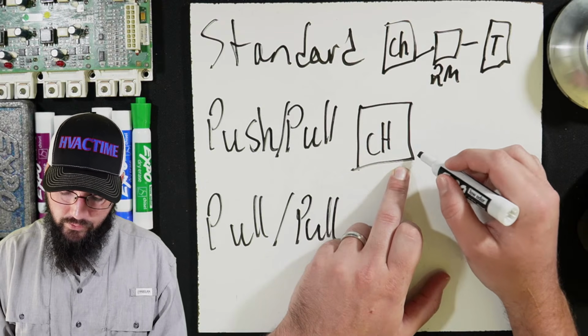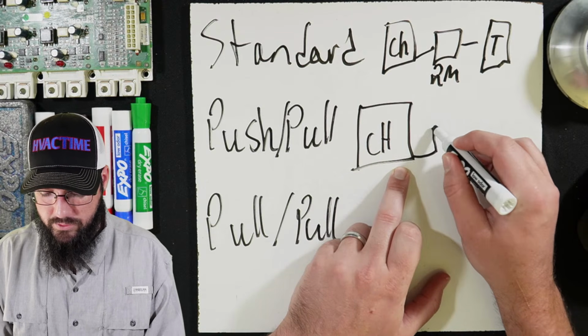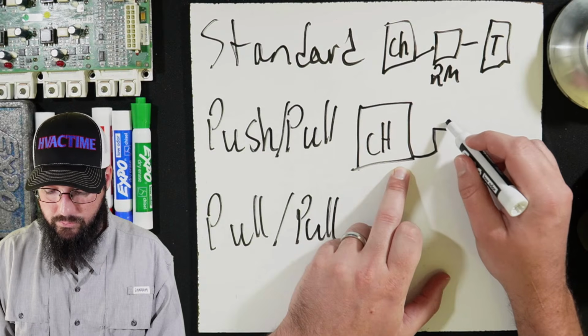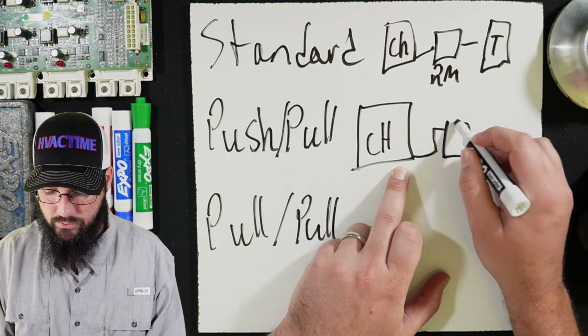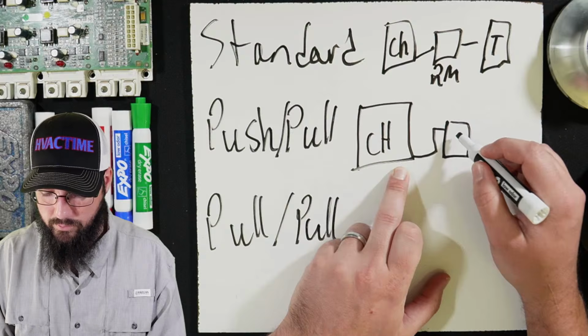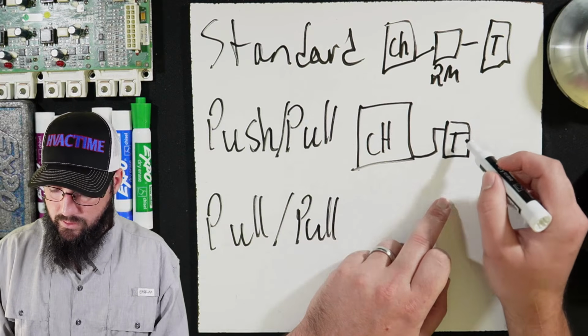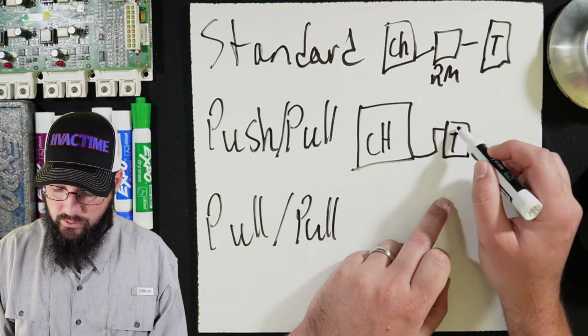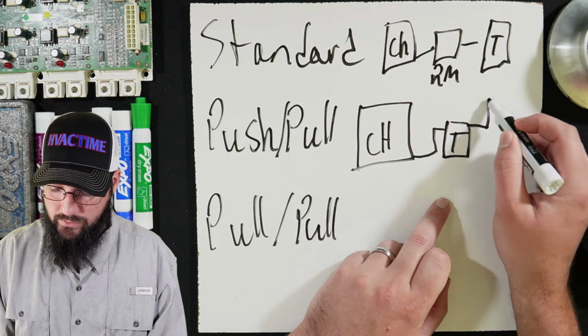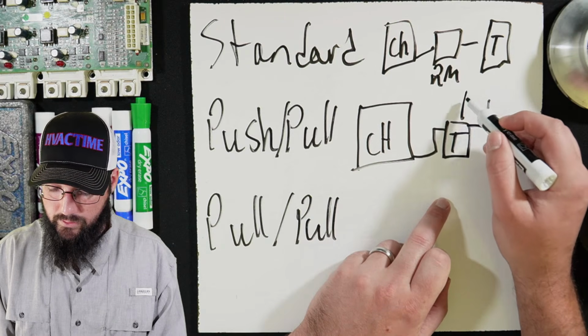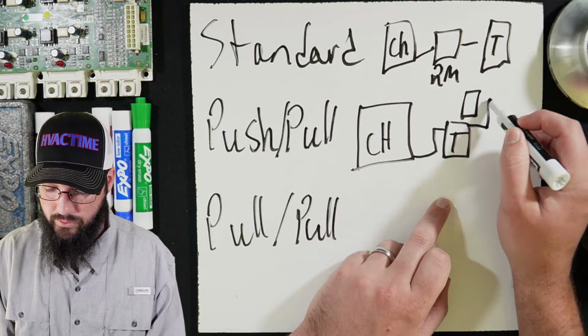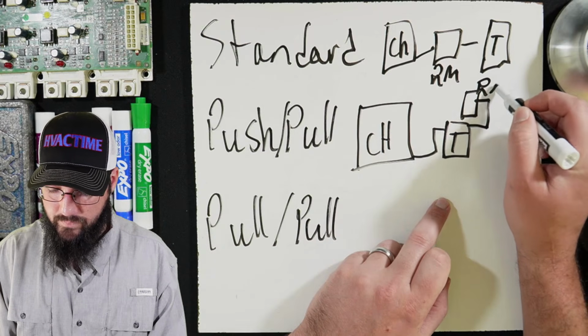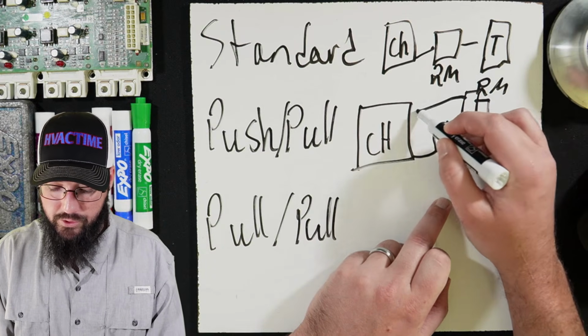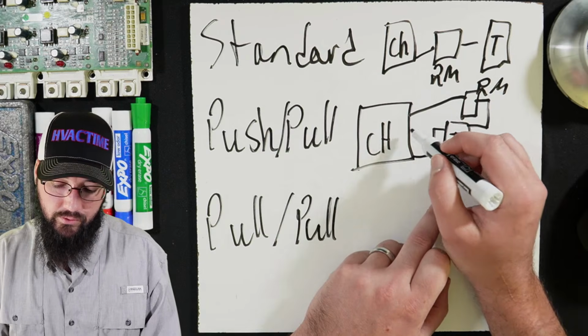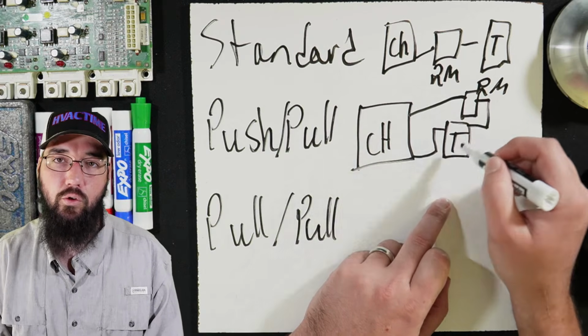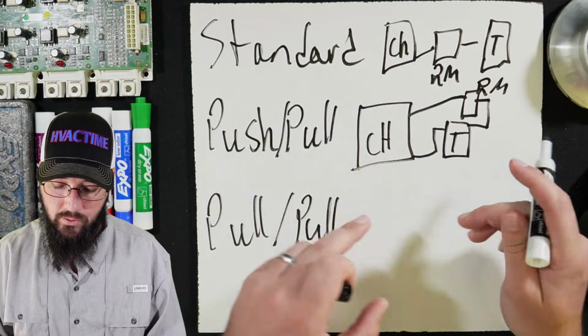So for the chiller, we're going to come out of the bottom of the chiller where we can get the liquid refrigerant. And that's going to come into a capture tank or a recovery tank. From there, it's going to come into the liquid port. We're going to come out of the vapor port into our recovery machine. And the recovery machine is going to push that vapor back into the chiller, and it creates this whole loop or cycle. Okay, this is a push-pull.